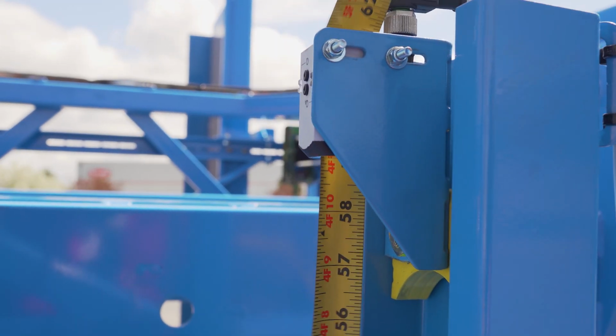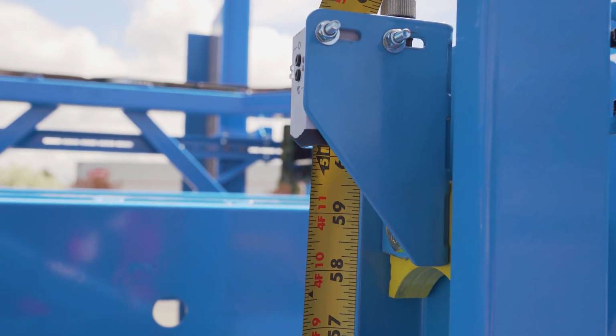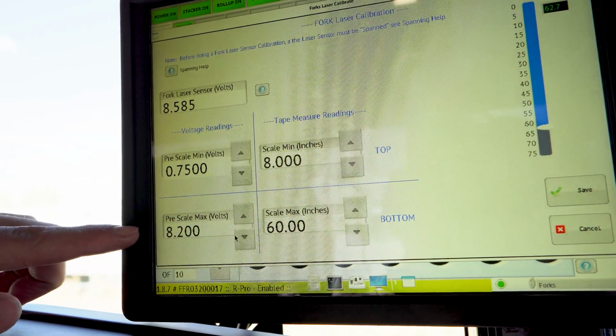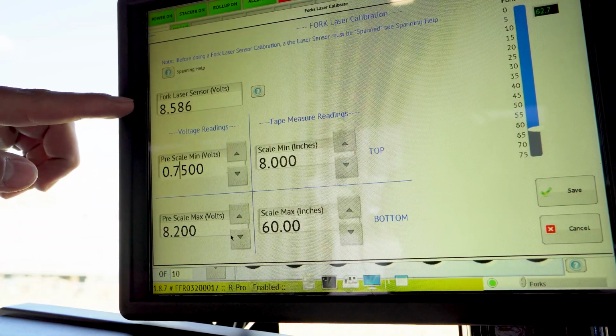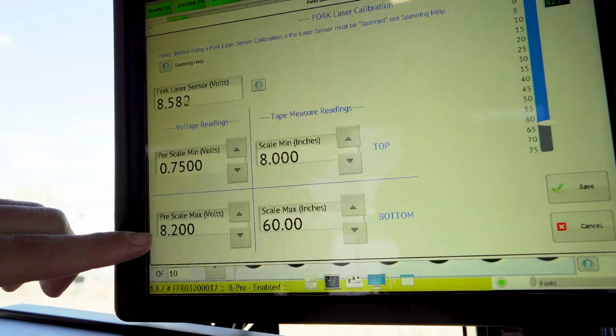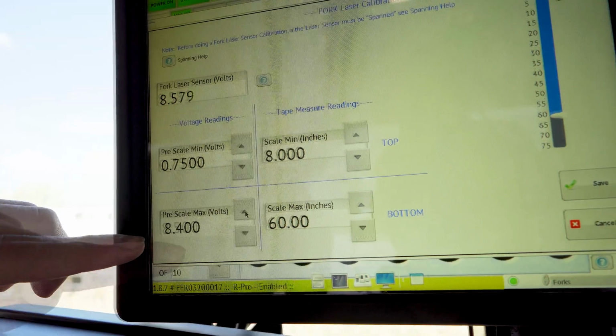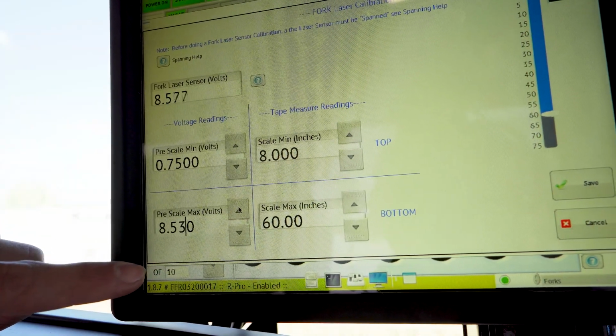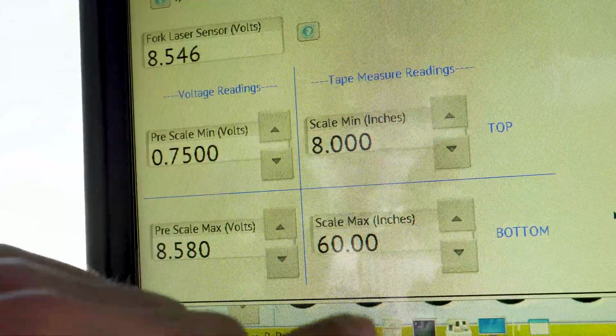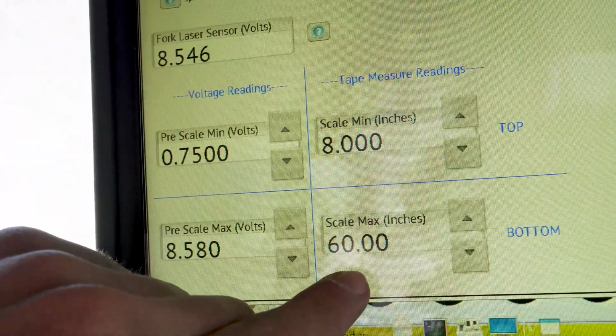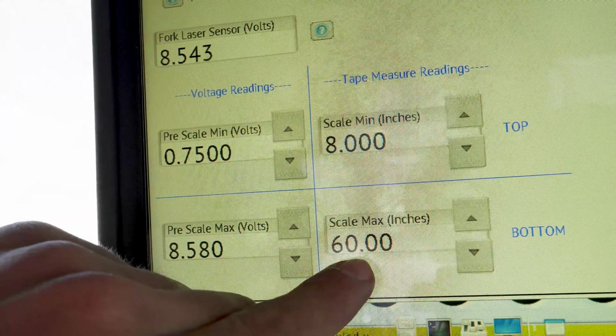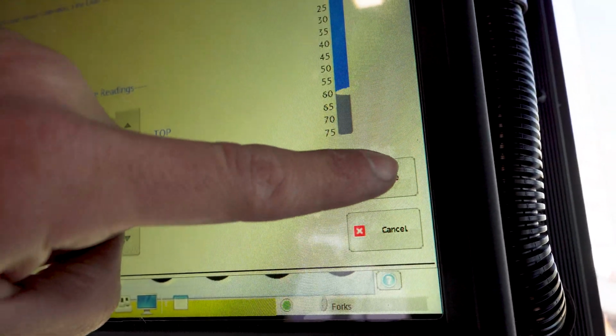So now we need to drop our forks all the way to the bottom where it's reading 60 inches on our tape measure. As soon as we're reading exactly 60 inches, we need to set our pre-scale max voltage setting to whatever the fork laser sensor volts are reading now. So we're gonna change this to 8.58. We need to make sure that our scale max inches is set to 60 inches, which is what our tape measurement reading is. So now that we've set our voltage settings, we can go ahead and click the save button.